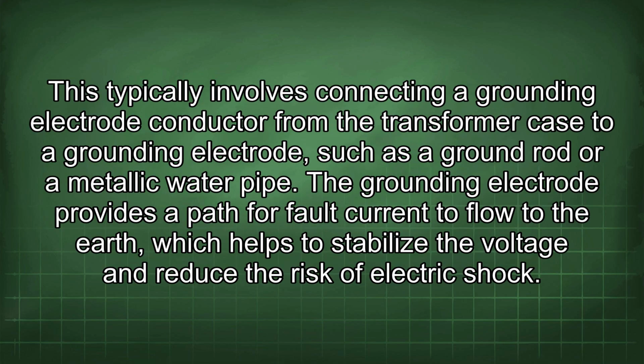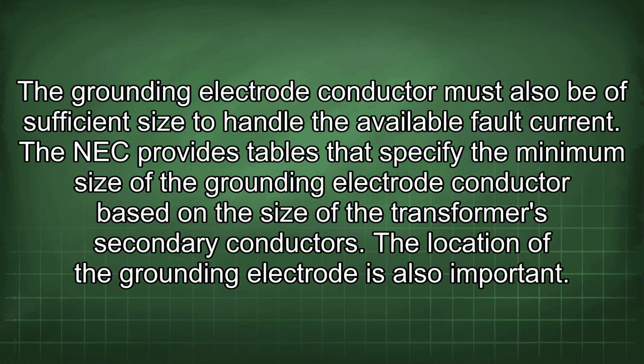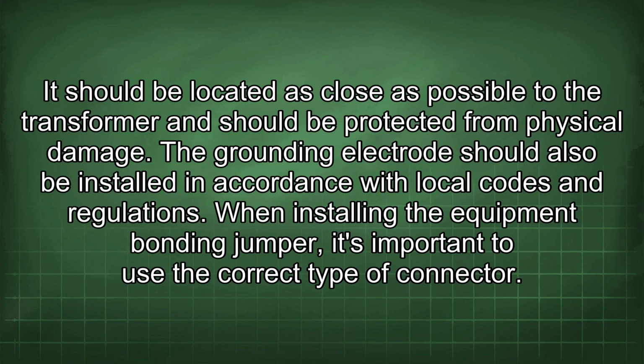This typically involves connecting a grounding electrode conductor from the transformer case to a grounding electrode, such as a ground rod or a metallic water pipe. The grounding electrode provides a path for fault current to flow to the earth, which helps to stabilize the voltage and reduce the risk of electric shock. The grounding electrode conductor must also be of sufficient size to handle the available fault current. The NEC provides tables that specify the minimum size of the grounding electrode conductor based on the size of the transformer's secondary conductors. The location of the grounding electrode is also important. It should be located as close as possible to the transformer and should be protected from physical damage. The grounding electrode should also be installed in accordance with local codes and regulations.